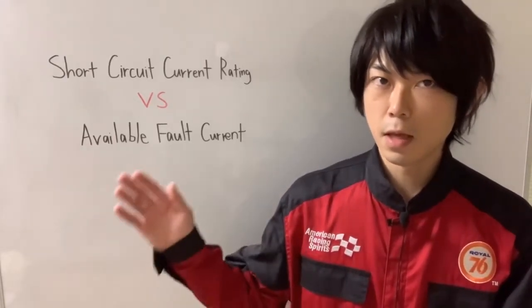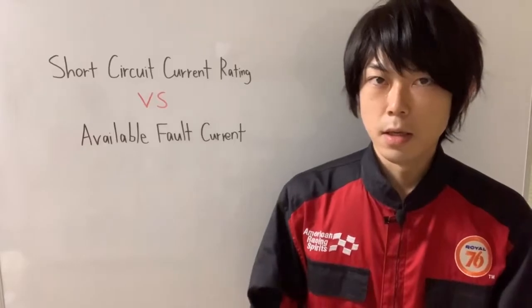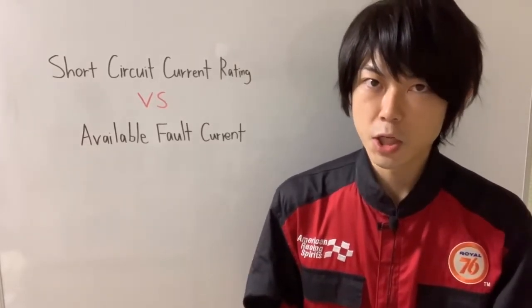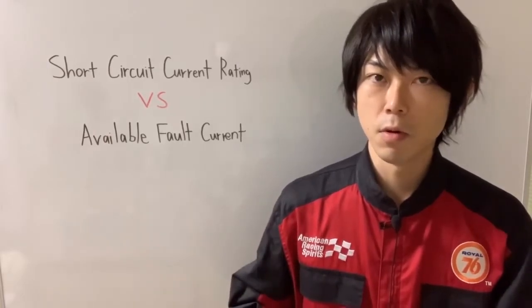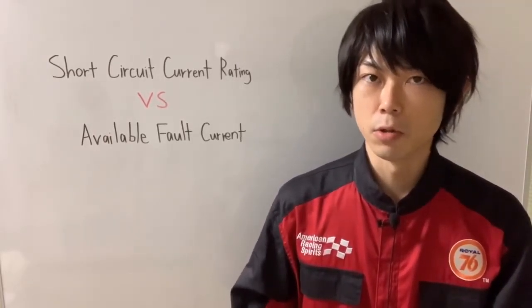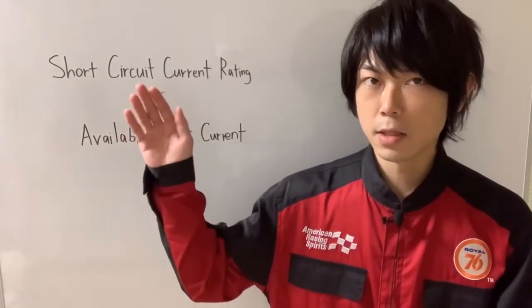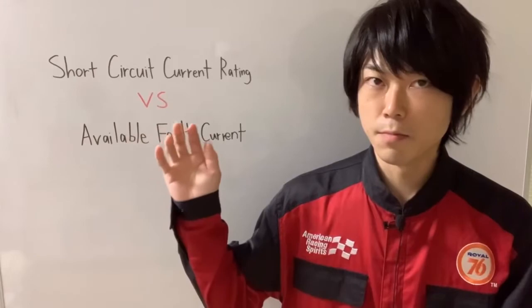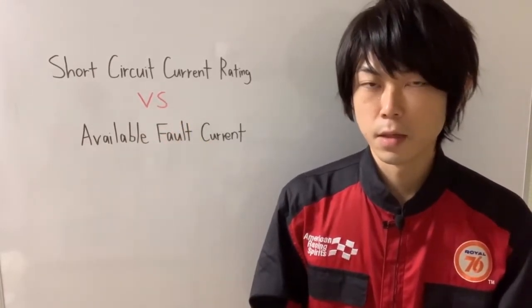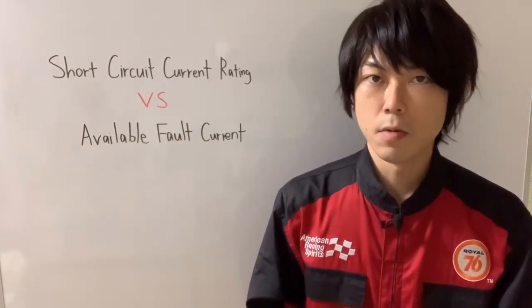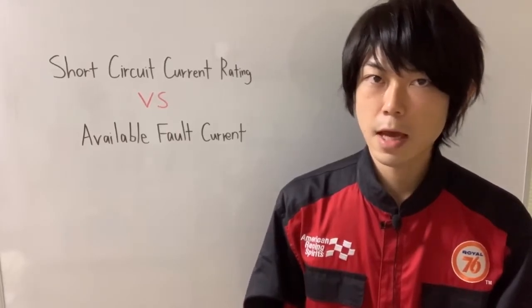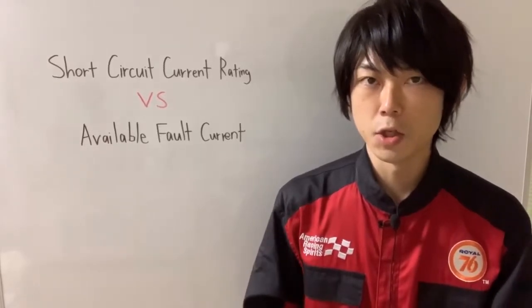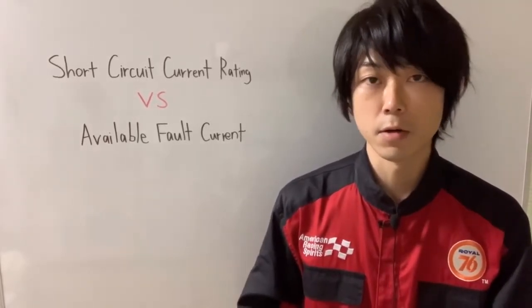On the other hand, available fault current is not an equipment rating but the amount of objectionable current that will flow at any point of our system as fault. So SCCR should not be less than the maximum available fault current. This concept is to eliminate downtime and increase worker safety. It must be taken into account when an engineer analyzes any power system.